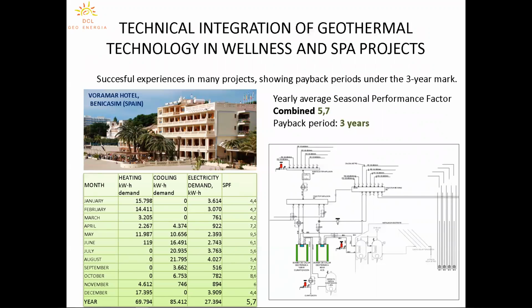Many heat pumps are able to combine the production of heating and cooling with circulating pumps integrated into the heat pump, so the area is usually smaller than with conventional systems. Just picture a technical room with 2 boilers, because usually they are doubled for safety and security of heat production. We need to install external units of chillers on the rooftop, and we need to double the amount of circulating pumps. So we're usually able to reduce the mechanical area needed by about 30%.